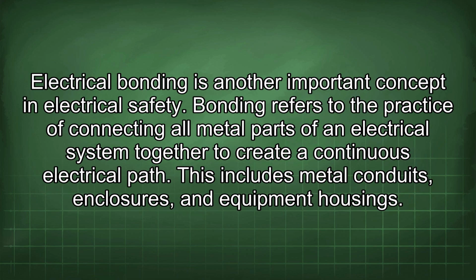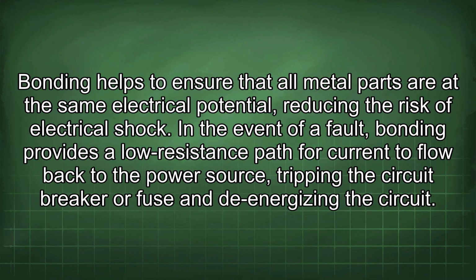Electrical bonding is another important concept in electrical safety. Bonding refers to the practice of connecting all metal parts of an electrical system together to create a continuous electrical path. This includes metal conduits, enclosures, and equipment housings. Bonding helps to ensure that all metal parts are at the same electrical potential, reducing the risk of electrical shock. In the event of a fault, bonding provides a low-resistance path for current to flow back to the power source, tripping the circuit breaker or fuse and de-energizing the circuit.